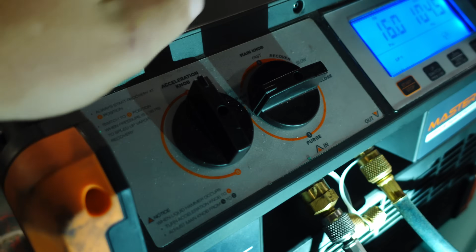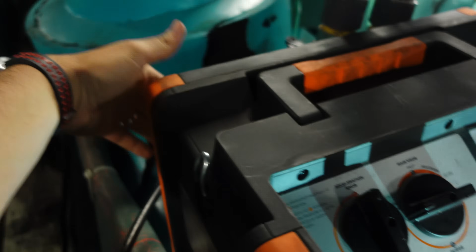So I got clarification as to exactly what these knobs are doing a little more. The first thing, on the push-pull: what makes the push-pull setting different from the recovery setting is the push-pull bypasses the subcooler on the back. There's a set of valves internally that will skip that cooler in order to not have it restrict anything in the system, which if you're doing a push-pull method, you don't really need a subcooler to begin with. So that's what push-pull is going to give you. And then if you go through recovery, obviously your refrigerant flow is going through the subcooler at that point.